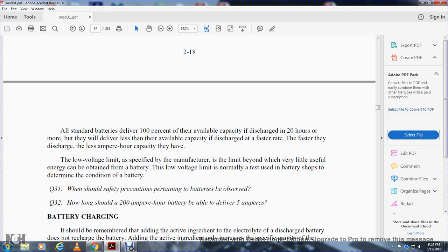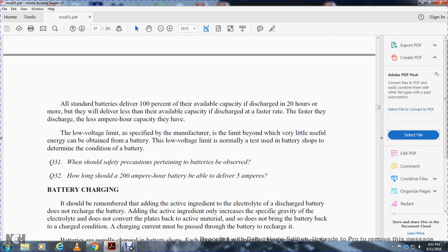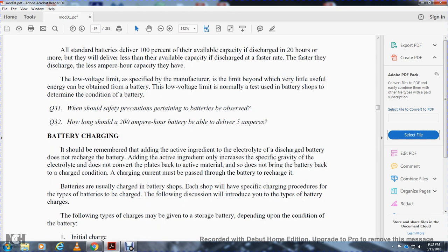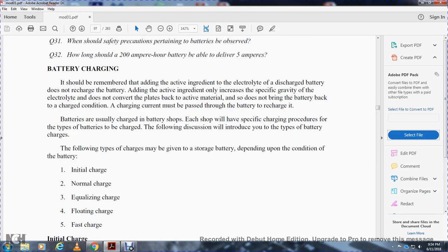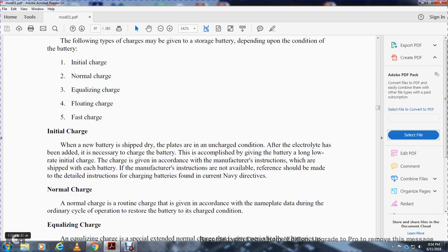Question 31: What safety precautions pertaining to batteries should be observed? Question 32: How long should a 200 ampere-hour battery be able to deliver 5 amperes? Battery charging: adding active ingredient or electrolyte to a discharged battery does not recharge it; adding active ingredient only increases the specific gravity of the electrolyte but does not convert the plates back to active material. A charging current must be passed through the battery to recharge it.